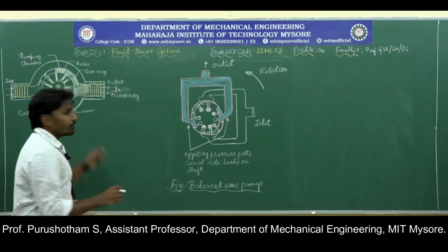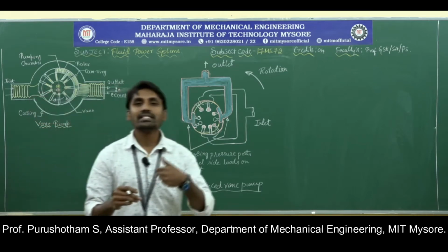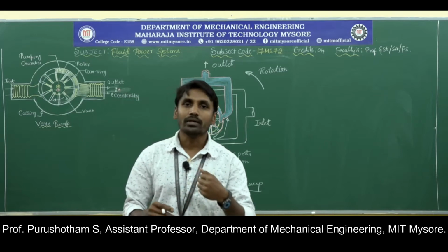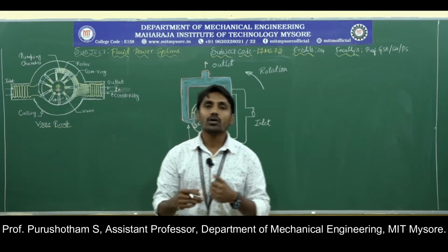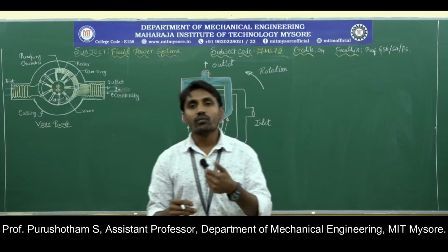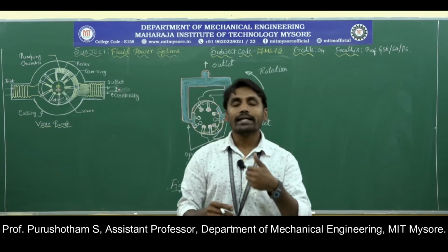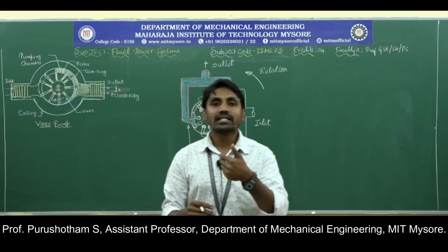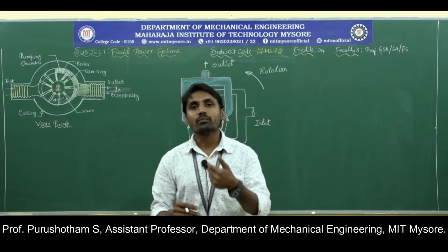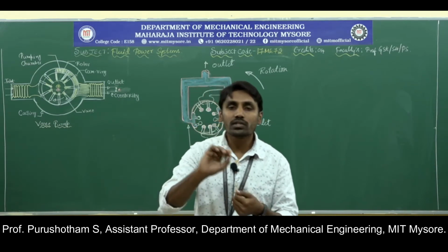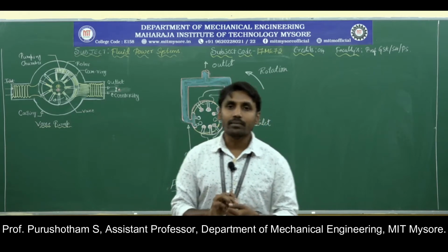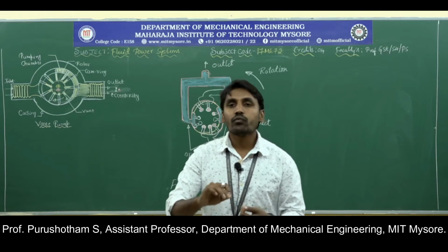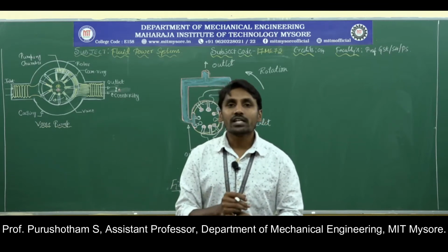Coming to vane pumps, these come under positive displacement rotary type pumps. The working principle of these vane pumps involves increasing volume and decreasing volume. When the volume increases, it creates a cavity that permits atmospheric pressure to force the fluid into the inlet chamber. When the volume decreases, the fluid is forced out into the discharge port.